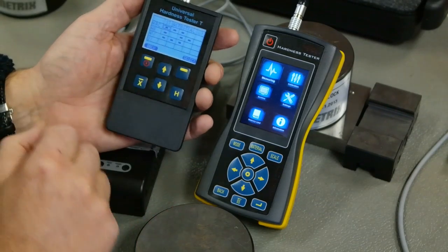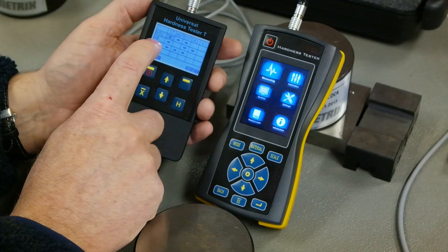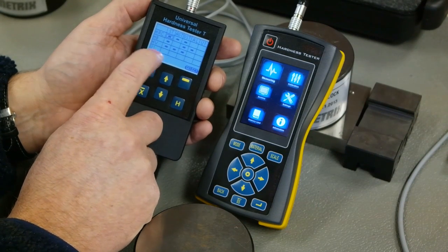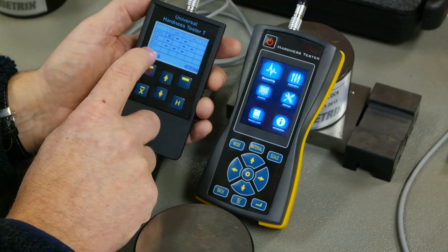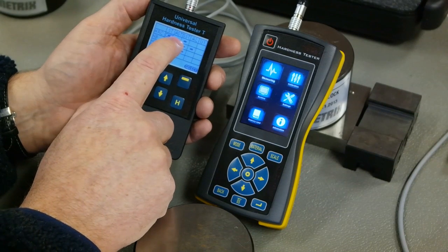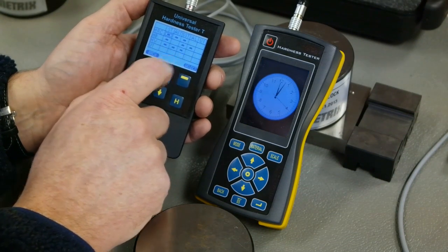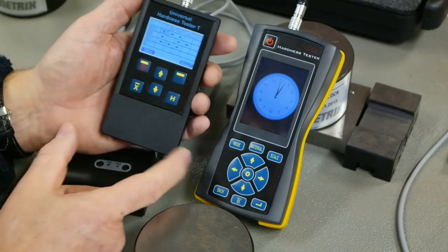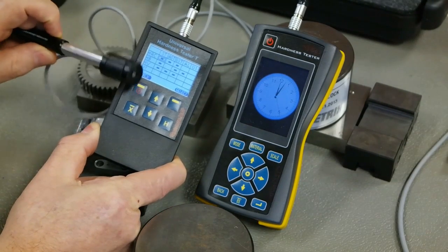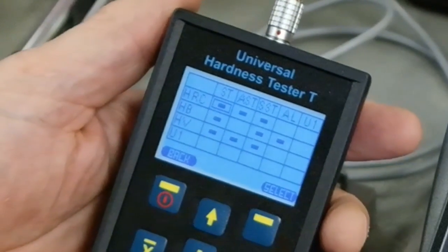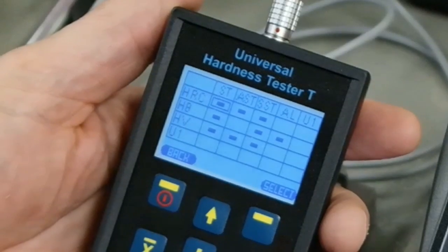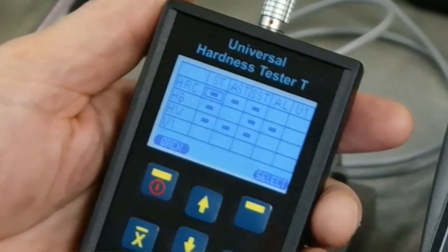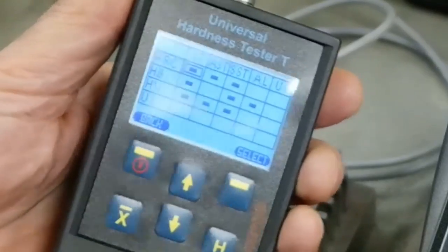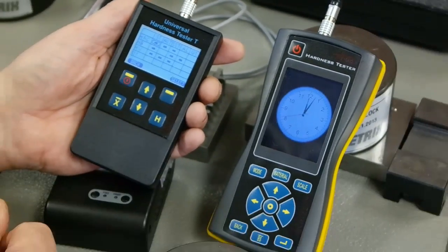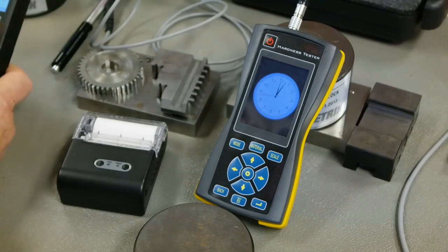Calibration. Here you can see this is the display, so we have HRC, Brinell, Vickers, and then a user-defined one here, so you might want to do Shore perhaps. Here we have steel, stainless steel, alloy steel, and aluminum, and then a user-defined one. These are pre-configured for the D-type probe, and on the UCI type probe, we pre-configure for steel for HRC, Brinell, and Vickers only. You can of course calibrate it for your own materials, even things like titanium, or very exotic stainless steels and so on. So I'll just power this one off.